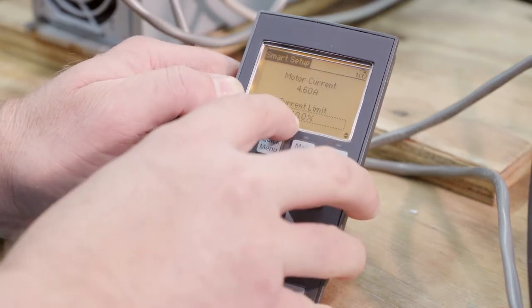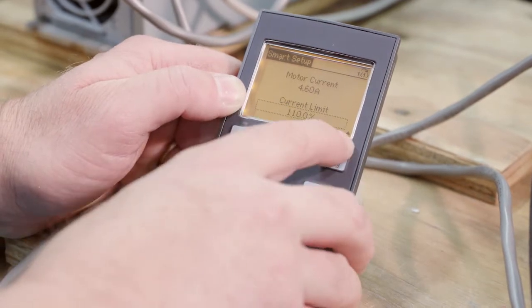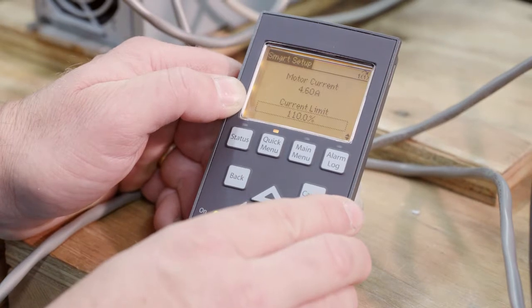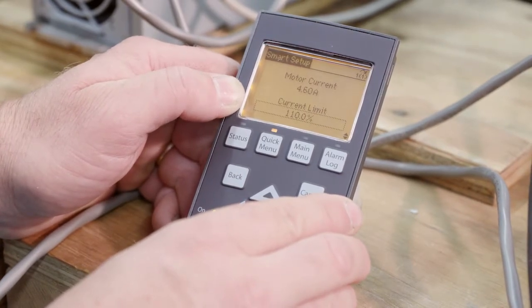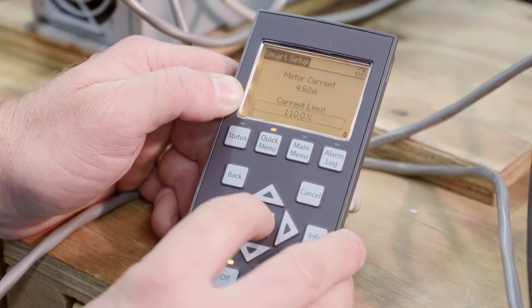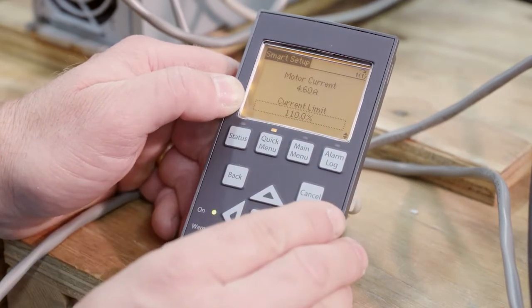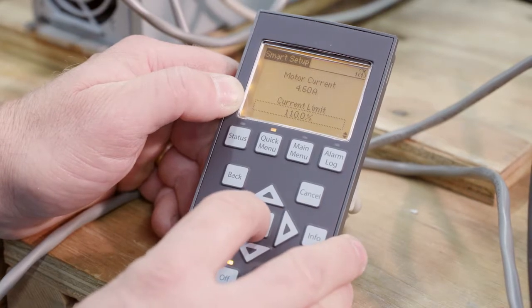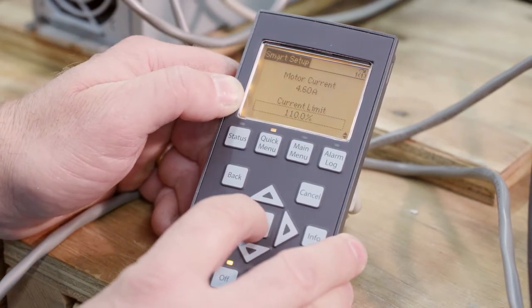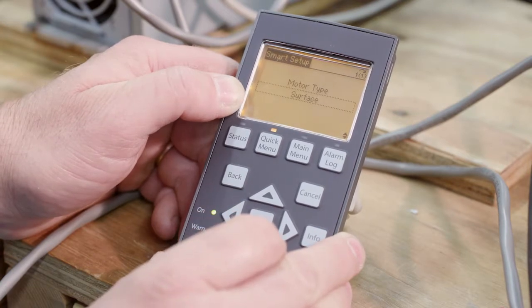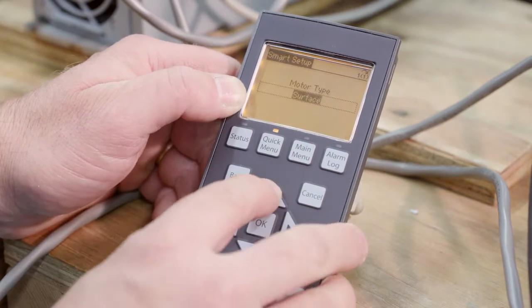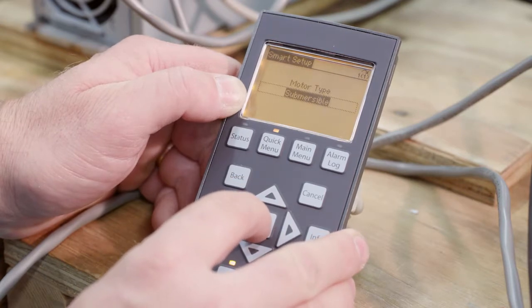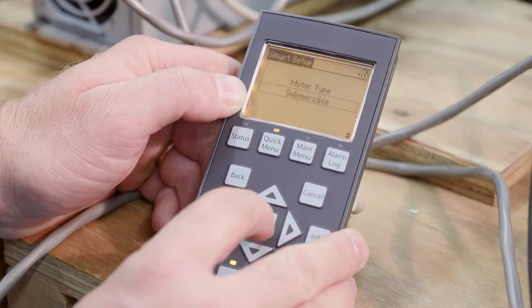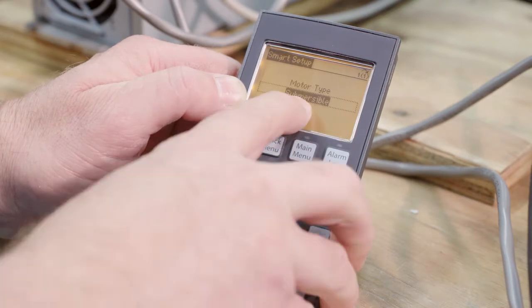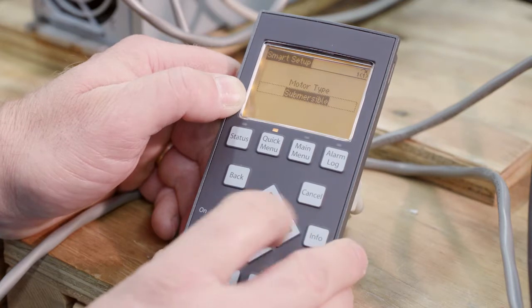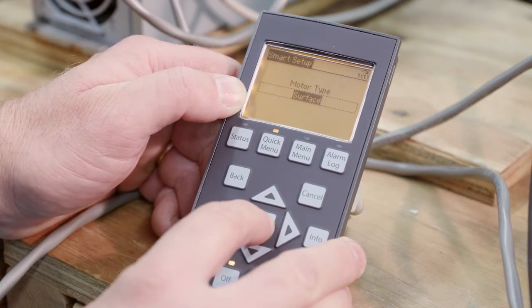Okay, so current limit. Current limit is service factor amps divided by nominal amps, and if I do the math, it's about 109, 110%. So there is a calculation that you need to do with current limit: service factor amps divided by nominal amps. I'm okay with 110. So motor type, I have a surface motor. The other option would be submersible. These are important because if I change that to submersible, it's changing parameters in the background. So I have a surface motor here.